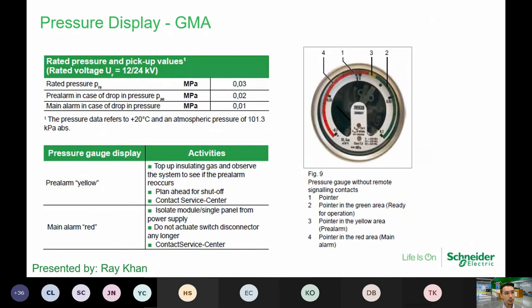Okay, so for the gas insulated switchgear, usually there will be a gas indicator. Like in here for the GMA series, we actually have a gauge. The gauge comes with three colors. The one in green generally points that it is healthy, and the rated pressure should be maintained at 0.03 MPa. But assuming there's a leakage, depending on the rate of the leak, you should generally go into this 0.02, which is the yellow region.